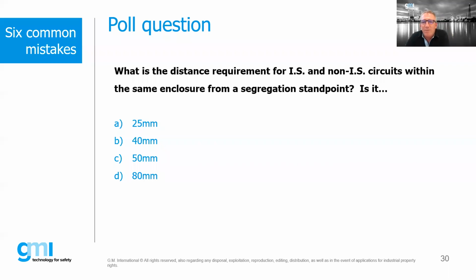Okay, I don't need to be Bob to say you are right - I was also paying attention to what you said. There you go. And by the way, if you really want to dazzle your friends with intrinsic safety knowledge, there are minimum requirements between IS and IS circuits, and that's 6 millimeters. So for future reference, if anybody asks what the minimum distance between each IS circuit is, it's 6 millimeters. And the minimum distance from IS to ground is 3 millimeters. So there you go. All right, let's close this.